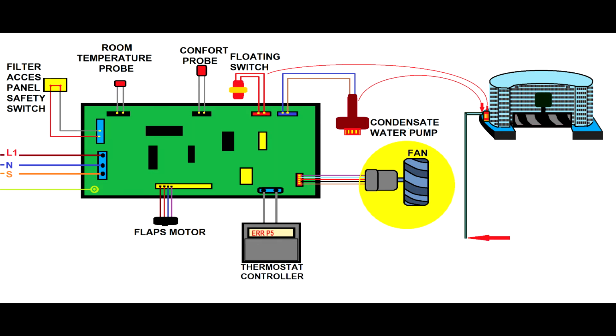Sometimes because of dirt, that little donut from the floating switch will not slide up and down the shaft, or the pump can be clogged or burnt, or there can be a lot of dirt in the drip tray. Then if the water stays too long in the drip tray, you will have this fault P5.